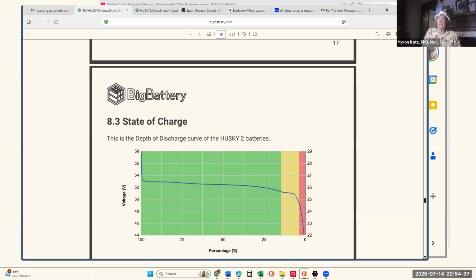If we did a calculation and ignored the fact that it's 80%, not 90%, or 90%, not 100%, just assume it's 100% per cycle. We have 5 kilowatt hours per cycle, and 5,000 cycles. Multiply those together, that's 5 times 5 is 25, so 25 megawatt hours or so you'd get out of this over the life of the battery. But it would be like 1/10 of that with the lead acid battery, because it can only do 700 cycles, and that lead acid battery can only go 50% of its total capacity. So it's a tremendous difference in the amount of energy.